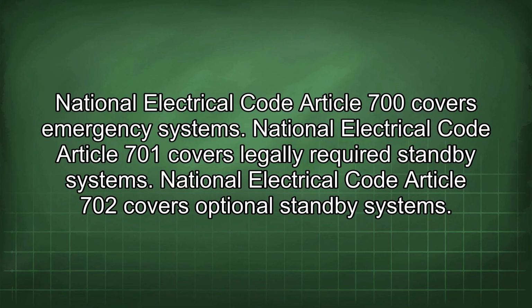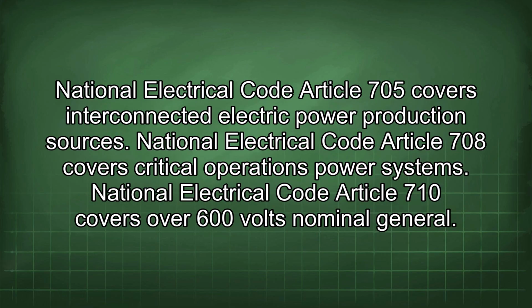National Electrical Code Article 700 covers emergency systems. Article 701 covers legally required standby systems. Article 702 covers optional standby systems. Article 705 covers interconnected electric power production sources. Article 708 covers critical operations power systems. Article 710 covers over 600 volts nominal, general.